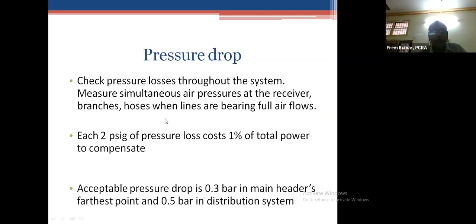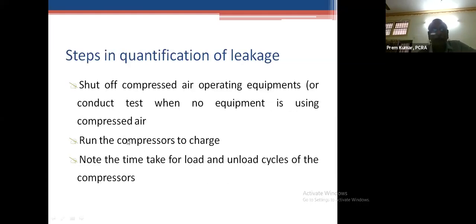So it will be a good practice to measure the pressure drop randomly from time to time. A pressure drop of 0.3 bar is very good. If it is 0.45 bar, one needs to see the leakage or the sizing should be taken care of. Many times during expansion, the compressed air is already in place, and the pipe sizing is ignored. So the leakage test needs to be done.